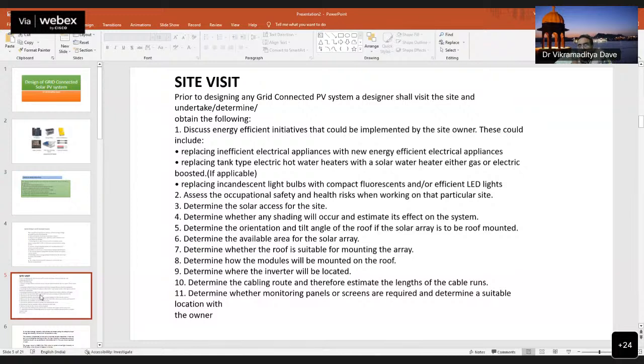Okay, now अब आपने देखा होगा कि ये सोलर पैनल किसी एंगल पर झुके रहते हैं। ठीक है, तो वो एंगल भी डिसाइड करना ये भी सोलर इंजीनियर का काम है। जिसको नहीं मालूम है उसको लगता है कि कोई ऐसे ही कुछ नया दिखाने के लिए उसको झुका देते होंगे। नहीं, it has some scientific logic behind it, that why these panels are being tilted, these panels are being tilted as per the scientific rule. They are tilted at an angle equal to the latitude of that city.